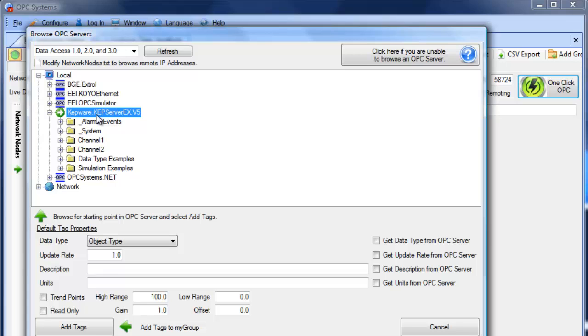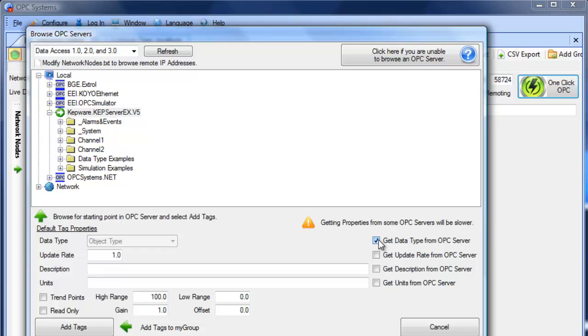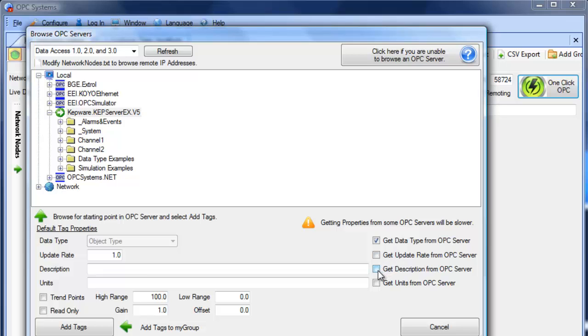For the one-click database feature to work properly, you will also want to specify to get the data type from the OPC server. So each opcsystems.net tag has a specific data type of, say, a single, a double, a string, a boolean. So we need those data types to be defined in the opcsystems.net tag, and this is the way to automatically get those data types from the OPC server.